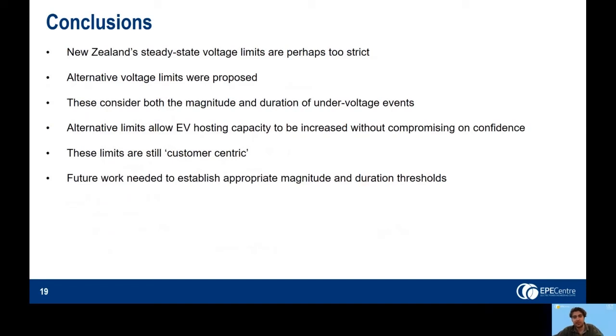These results show that perhaps the steady-state voltage limits in New Zealand are a little too strict. Alternative voltage limits were proposed which consider both the magnitude and duration of undervoltage events. These allow EV hosting capacity to be increased without compromising on confidence. The alternative limits are still customer-centric because they are based on the worst affected customer in the network and during the week of the year with the peak load.